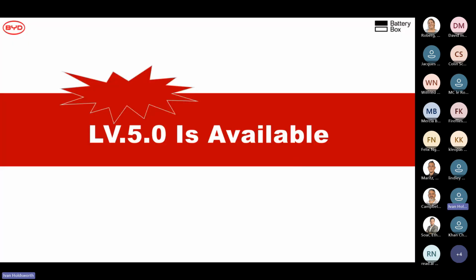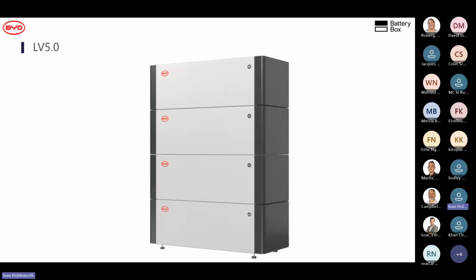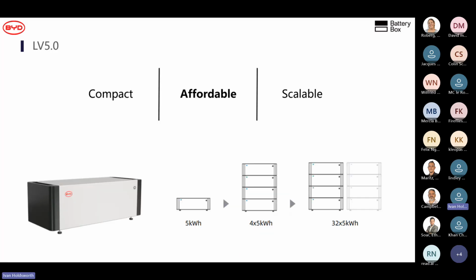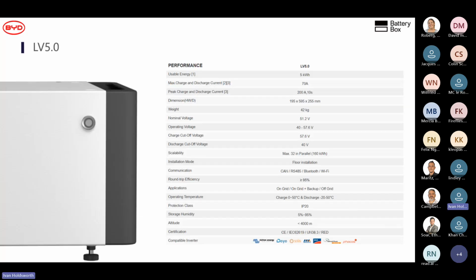And then we're just going to have a quick run through of the LV5. This is the LV5. It's 5 kWh per module, and you can have up to 32 of them. And then you've got some specs. It's a 0.7C battery, 0.7C charge and discharge at max, and the peak is 200 amps for 10 seconds. And you can have up to 32 of them, for 160 kilowatt hours.